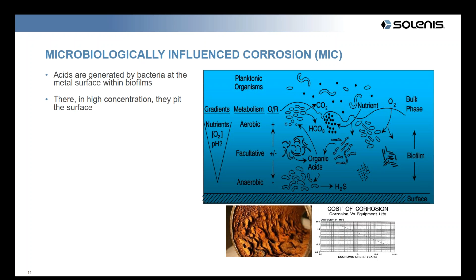And the byproduct of their respiration is typically an acid, and they're generated at the metal surface where they're trapped now. They lower the pH, and they cause corrosion. And the kind of corrosion that they cause is pitting type corrosion, which is the worst corrosion of all, because while a generalized corrosion may be 4 or 5 mils per year, this is really concentrated, and it may be 50 or 60 mils per year, and you've got a pinhole leak.